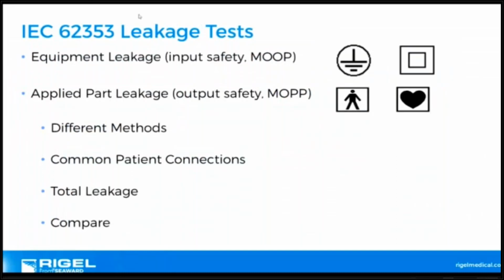And then we've got the similar classification of our means of operator protection, class 1, class 2, and our means of patient protection with BF and CF. Note B isn't included because we only use mains on applied part settings in 62353. So what happens if you didn't stress that with the 60601, but let's say we've got our medical device, right? And it's earthed, and it has an applied part. But we know that B applied parts are type B, earth referenced.